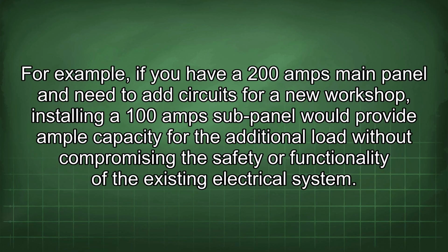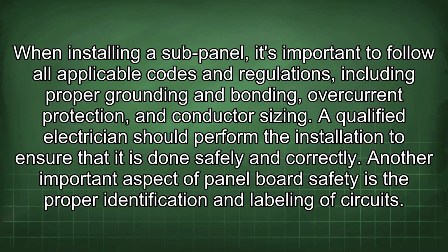For example, if you have a 200-amp main panel and need to add circuits for a new workshop, installing a 100-amp sub-panel would provide ample capacity for the additional load without compromising the safety or functionality of the existing electrical system. When installing a sub-panel, it's important to follow all applicable codes and regulations, including proper grounding and bonding, overcurrent protection, and conductor sizing. A qualified electrician should perform the installation to ensure that it is done safely and correctly.